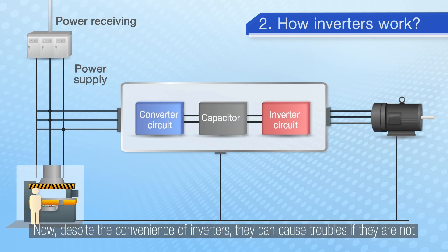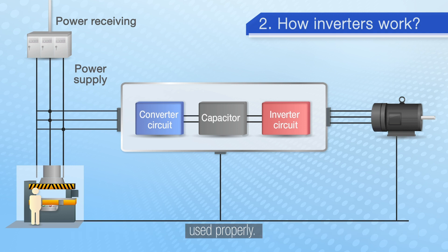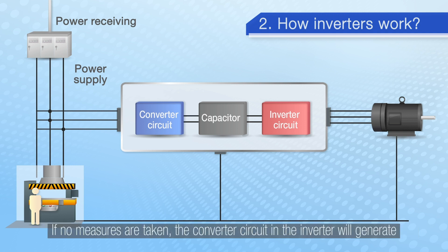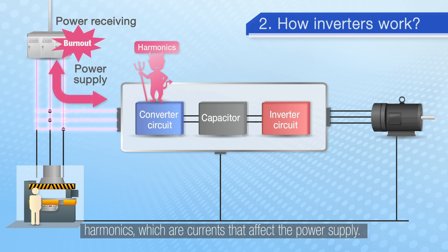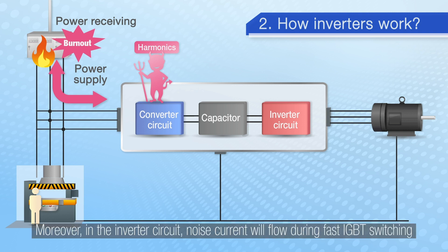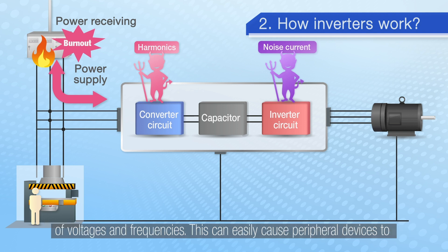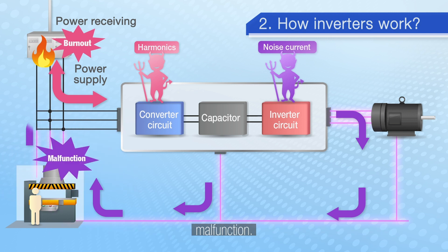Now, despite the convenience of inverters, they can cause trouble if they are not used properly. If no measures are taken, the converter circuit in the inverter will generate harmonics, which are currents that affect the power supply. Moreover, in the inverter circuit, noise current will flow during fast IGBT switching of voltages and frequencies, and this can easily cause peripheral devices to malfunction.